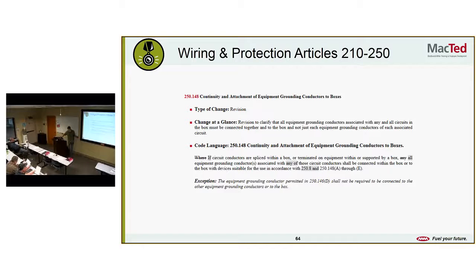Continuity and attachment of equipment grounding conductors to boxes. So here we're talking about junction boxes. A revision clarifies that all equipment grounding conductors associated with any and all circuits in the box must be connected together and to the box, not just the equipment grounding conductors of each associated circuit. If the circuit conductors are spliced within a box or terminated on equipment within or supported by a box, all equipment grounding conductors associated with any of those circuit conductors shall be connected within the box or to the box with devices suitable for the use in accordance with 250.8.